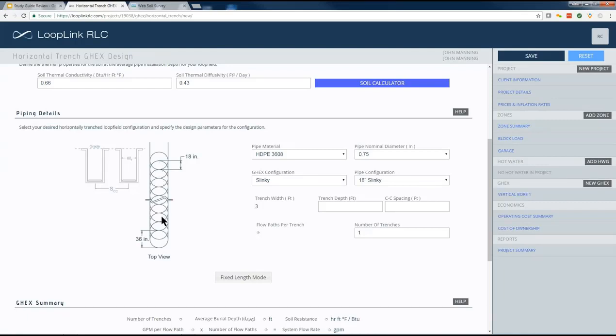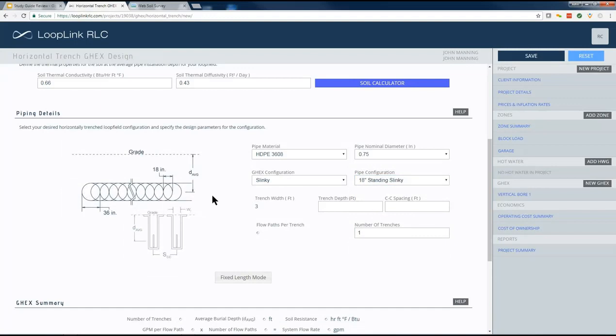So with a 36-inch diameter and an 18-inch pitch, each slinky loop overlaps half of the previous one. So that's what that means. And notice we've got an 18-inch slinky and an 18-inch standing slinky. There's no difference in the way they're constructed, except a standing slinky is standing on its side, just like this, in a trench that maybe you've dug with a chain trencher instead of a backhoe. So we allow you to specify those differently as well.